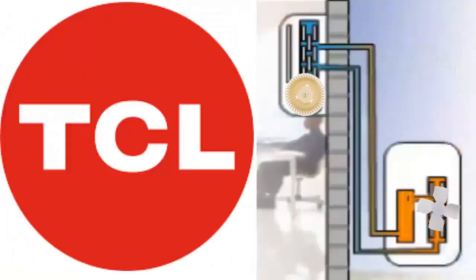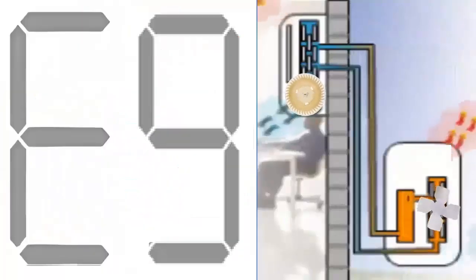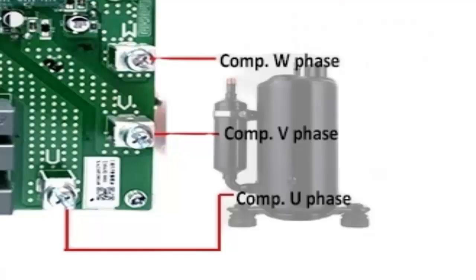Step 3: If the E9 error persists and occurs when the compressor starts or doesn't start at all, verify that the connection from the external electronic board to the compressor is correct.